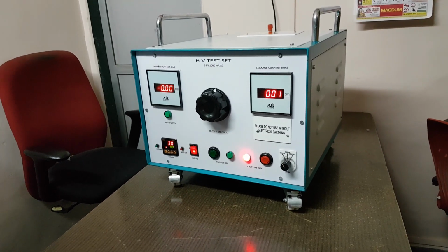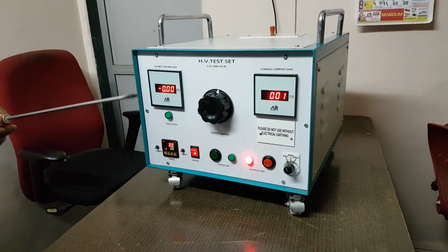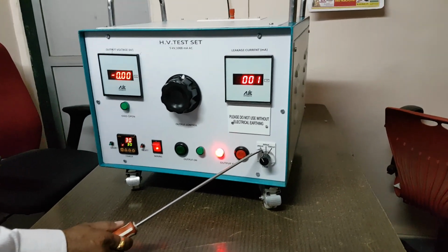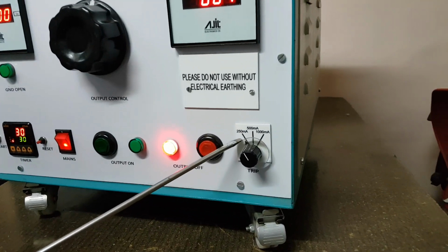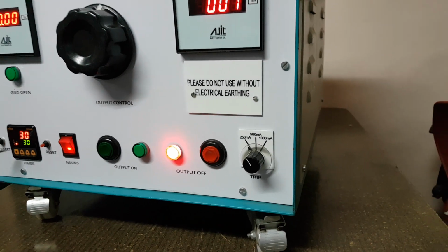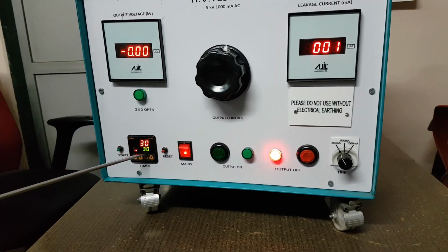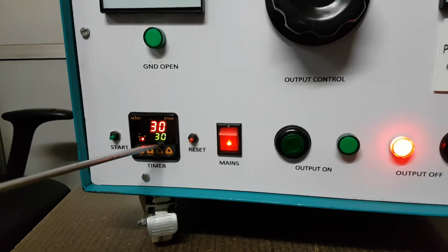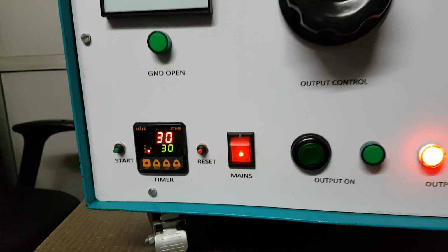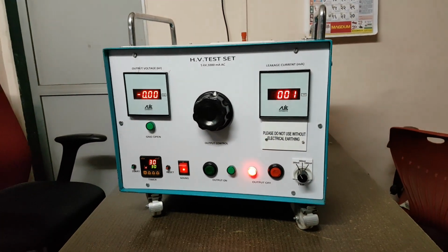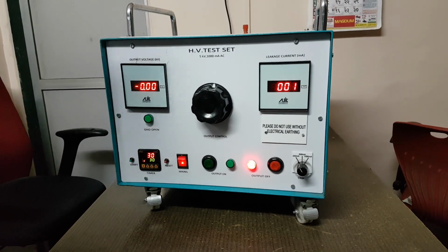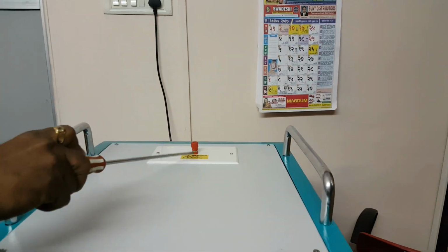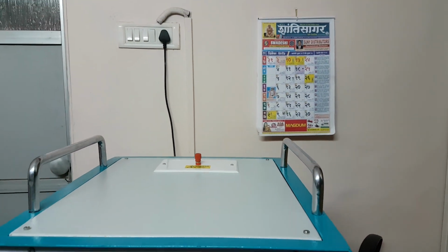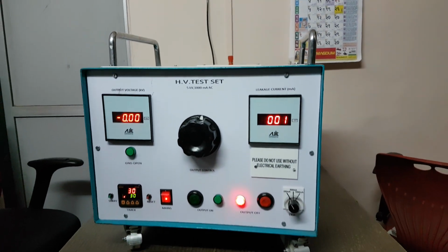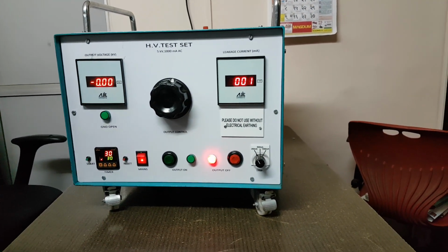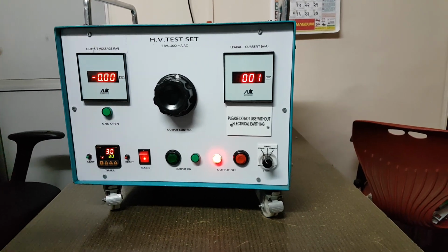This way we can use the timer. Now let's see the overall operation of the instrument. We have set the trip current limit at 250 milliampere here. Then we have set the test duration of 30 seconds on the timer. Okay, like this. Now what we have to do is connect the object under test across the output terminal and the ground terminal. This is the output terminal and the ground terminal on the back panel of the instrument. So we have to connect the object across the two terminals. Once the object is connected, then we can use the instrument.